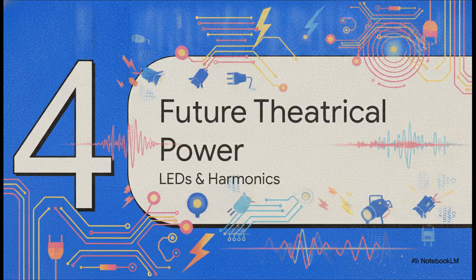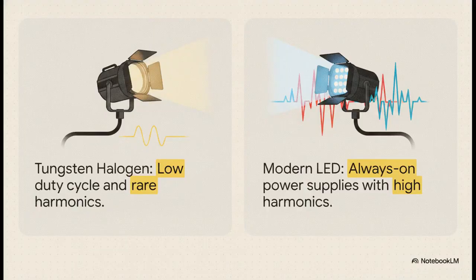Section 4. Future Theatrical Power, LEDs and Harmonics. Right now, the whole industry is undergoing a massive shift. We are rapidly replacing those historical tungsten halogen lamps with modern LED systems. Now, remember that hidden diversity safety buffer we talked about earlier, the one that saved our cables? It only existed because tungsten fixtures had a low duty cycle and rarely produced harmonics. But modern LED fixtures? They have switch mode power supplies that are energized and on all the time, even when the light isn't physically emitting anything. They introduce continuous, harmonic-rich loads to the grid, which fundamentally changes the electrical math of the entire theater.